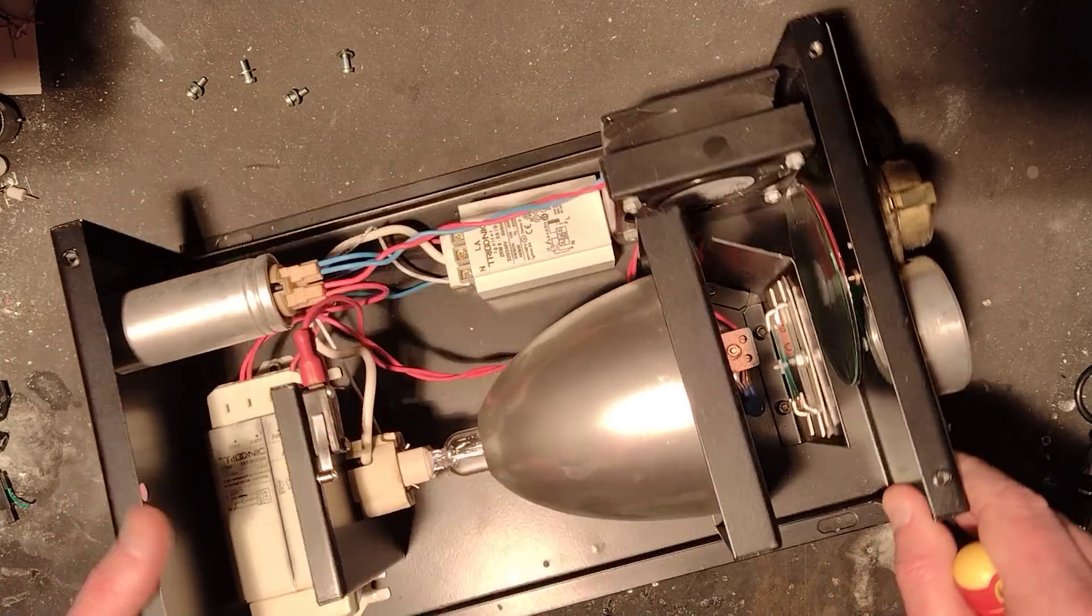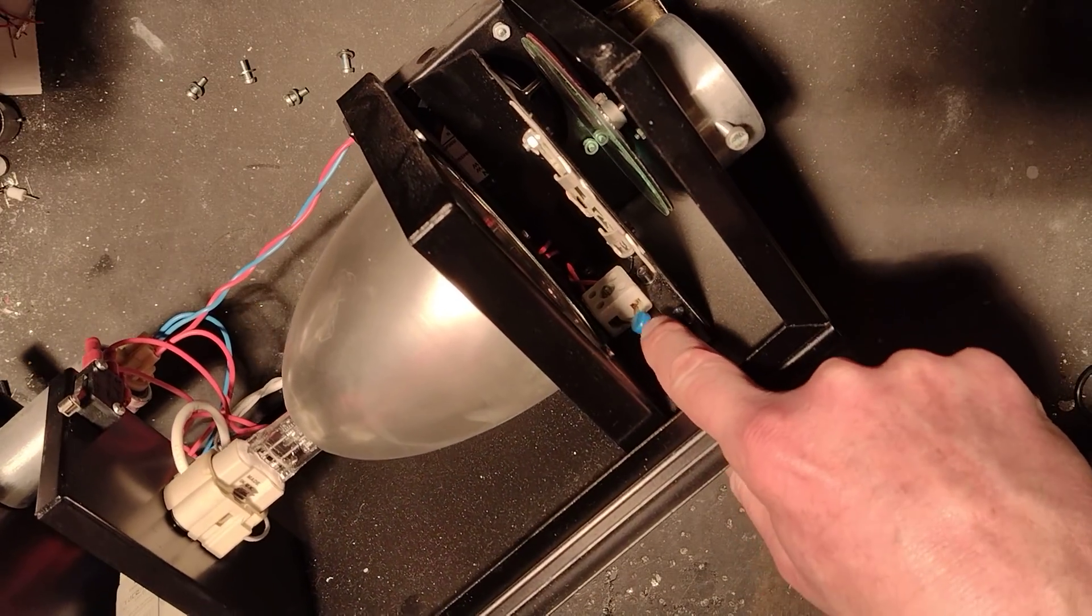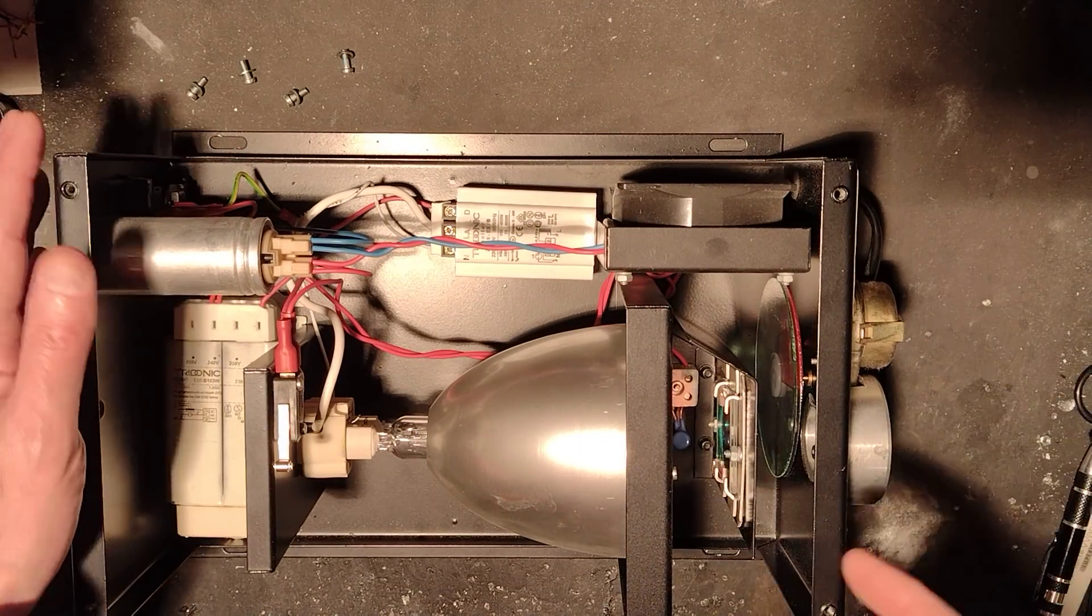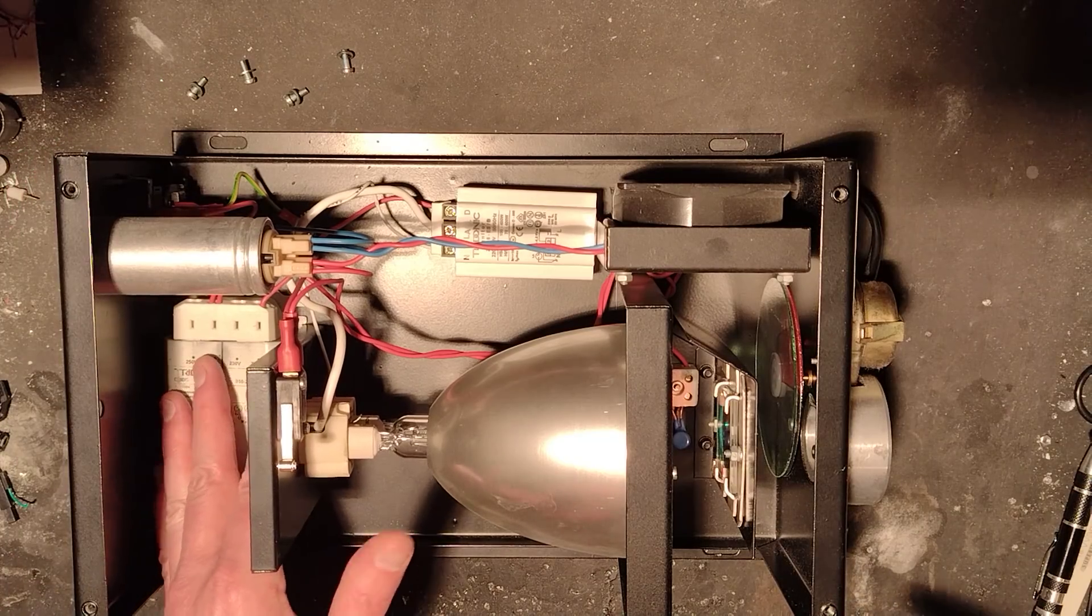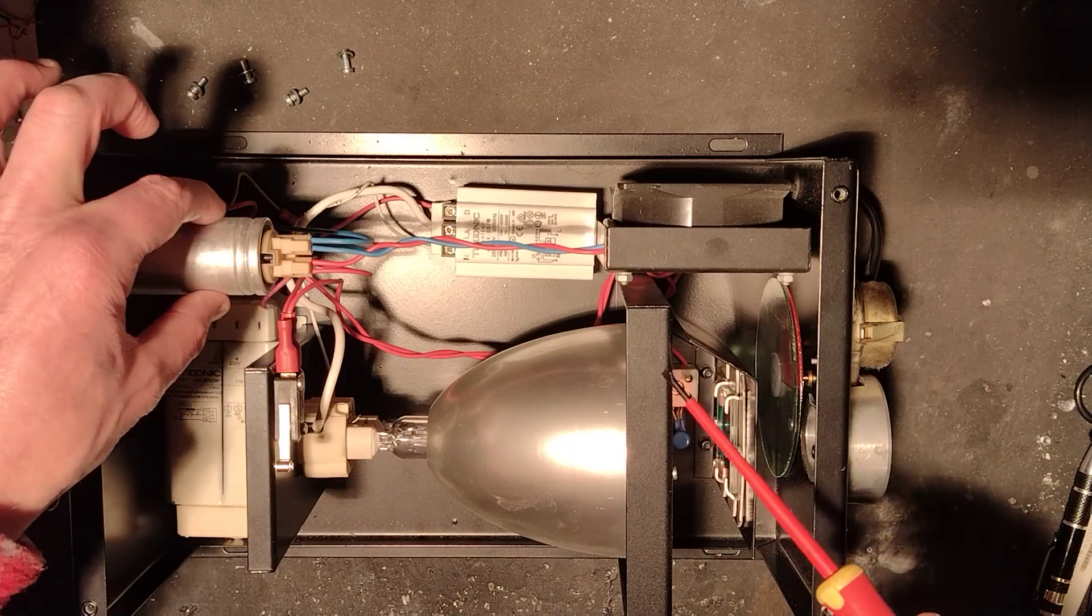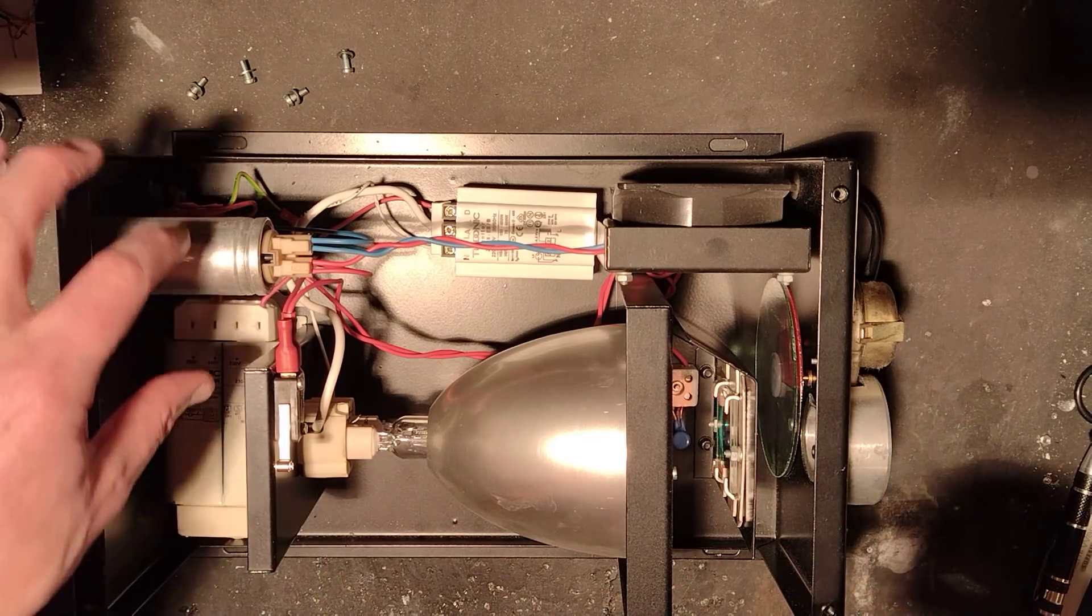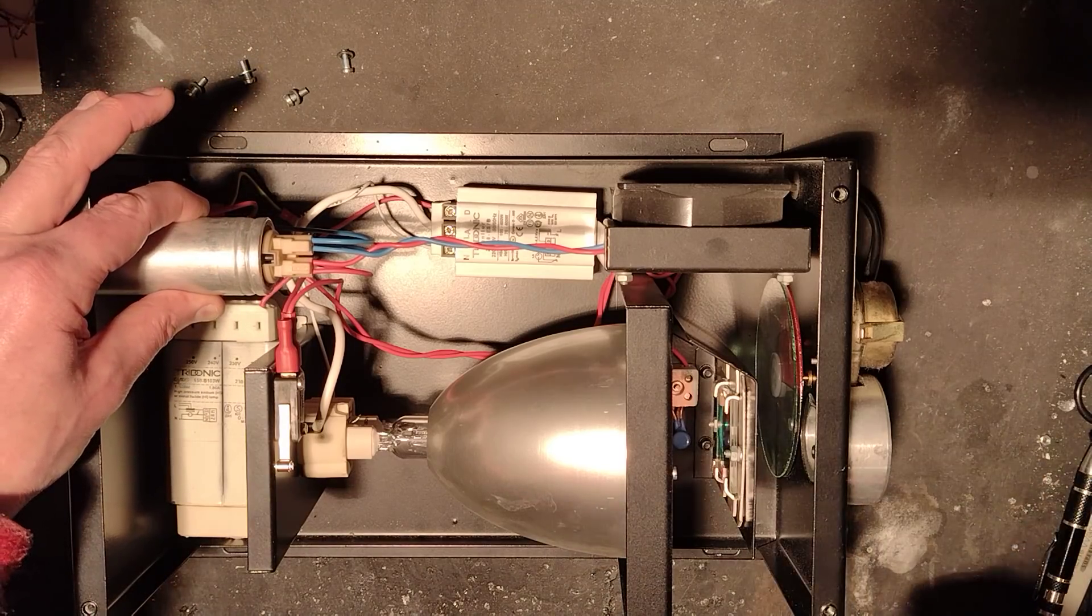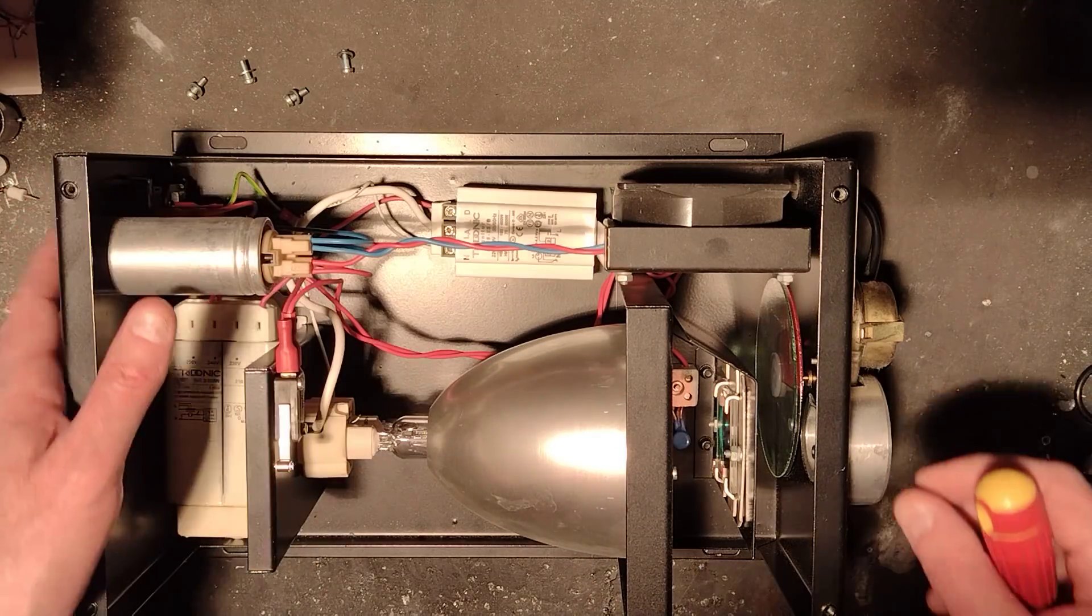The safety circuit, which this switch is a part of, then comes down to this little blue component down here, which is a thermal cutout. And it goes back and it feeds the rest of the circuit. It feeds the ballast at the back here, which limits the current through the lamp. It loops up and goes to this power factor correction capacitor, which just basically compensates the inductiveness of that. It is basically in parallel with the power supply.